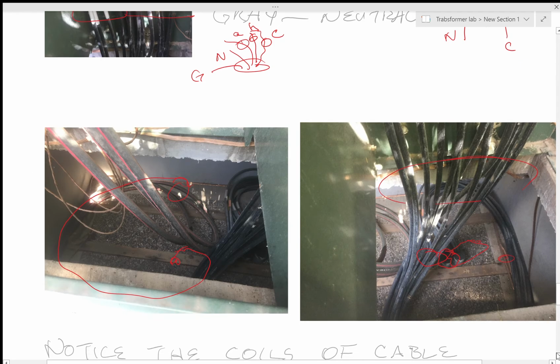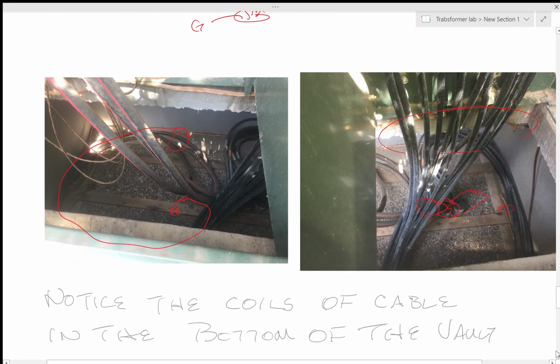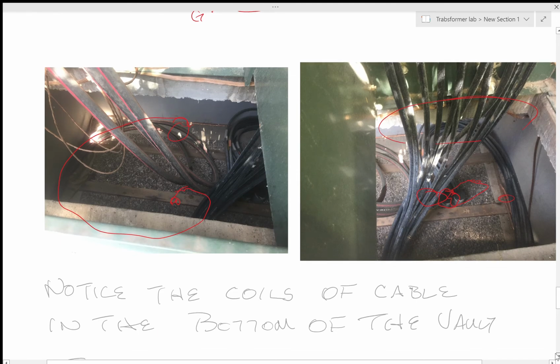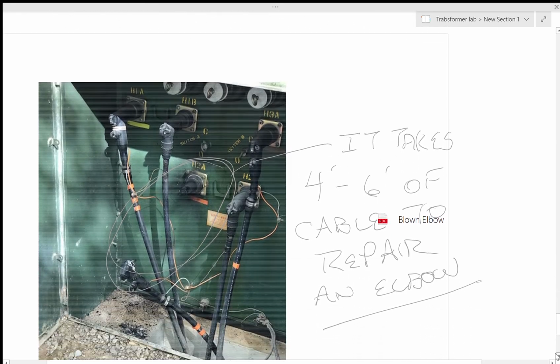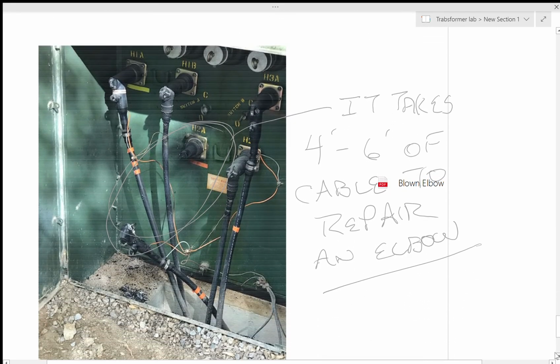Not a pretty sight. Okay, so notice that there are coils of wire in the bottom of this thing. There's spare wire in there. So the question is why is there spare wire in there? Well, I can tell you why. Because if I have to go in and one of these elbows goes bad, or one of those terminals goes bad, there you go. That's what happens when they go bad. They blow off. Notice there's the elbow. That elbow used to look like that elbow, which used to look like that elbow at the beginning of the presentation here. What happened? Well, we really don't know.